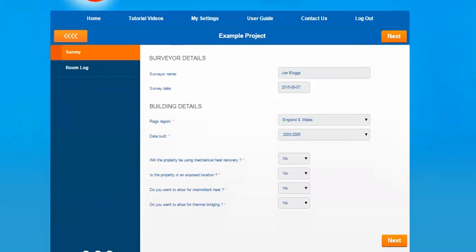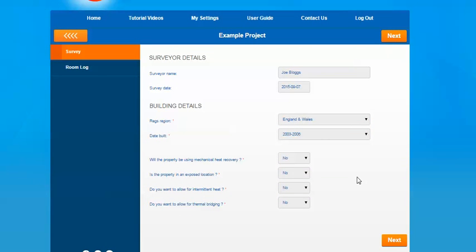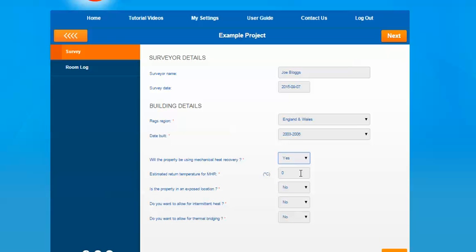We then move on to four questions about the property. First of all, will the property be using mechanical heat recovery? The reason this is included is that mechanical heat recovery can return a temperature back to the property and will provide some heat, so the heat pump won't have to work as hard to produce the required temperature. If you select yes, an option to allow an estimated return temperature will appear. For this example we'll put in a 10 degree return temperature.